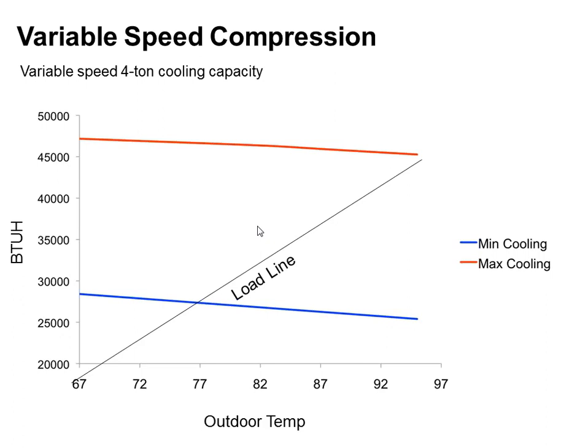So this gives you an example here. The lowest capacity and highest capacity lines for a 4-ton heat pump. This black line represents the load of your house, right? Before, we had it going the other direction because it was heating mode. Now we're in the cooling scenario. So now it starts down here with almost no BTUs at 65 degrees outside. And as it gets hotter outside, the line gets higher, which means we need more and more cooling capacity until we get up to, what are we at, 47,000 BTUs on a 95-degree day in this example. So normally I'd be shutting this thing on, off, 47,000 BTUs, 0. 47,000, 0. Giving you 55-degree cooling, 75-degree return air. 55 cooling, 75 return air. Clicking it on and off all day long.